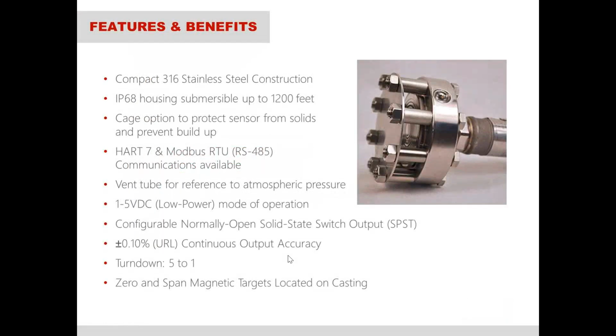The 815 LT is basically everything that I just said with the 815 PT. The main difference is there are some different process connection options, as well as it's submersible to a depth of 1,200 feet. It has an IP68 rated housing to that depth. Same stainless steel housing. We've added a cage diaphragm seal option to protect it, to have the sensor protected from any type of debris or contaminants and so on.